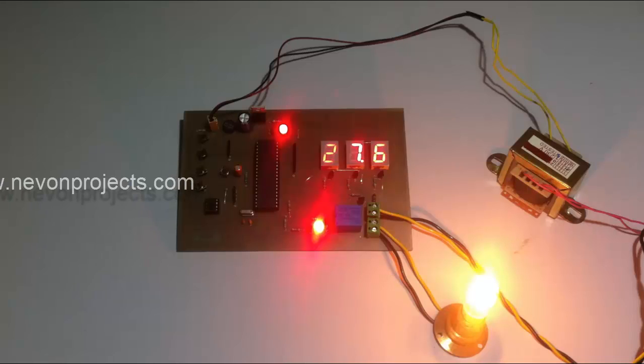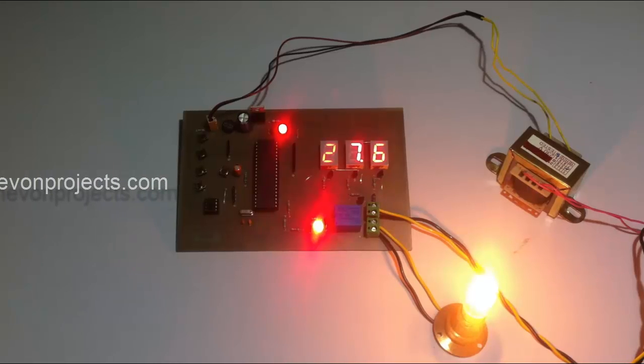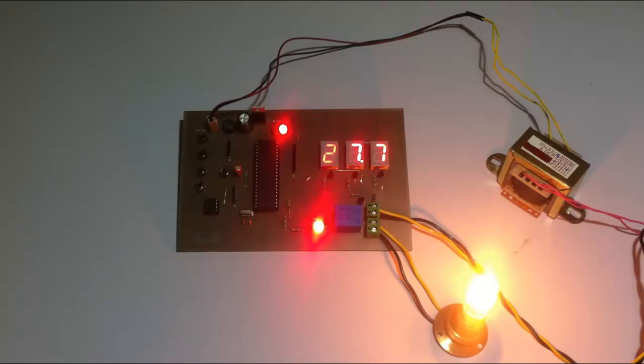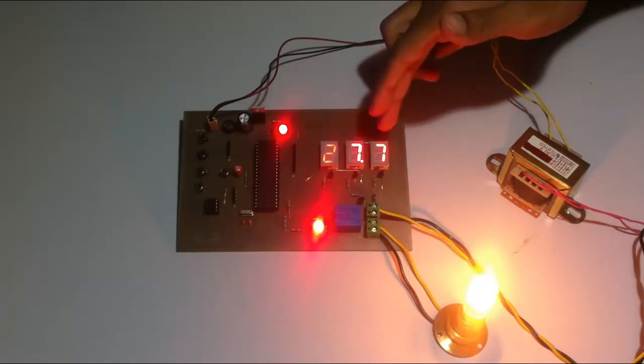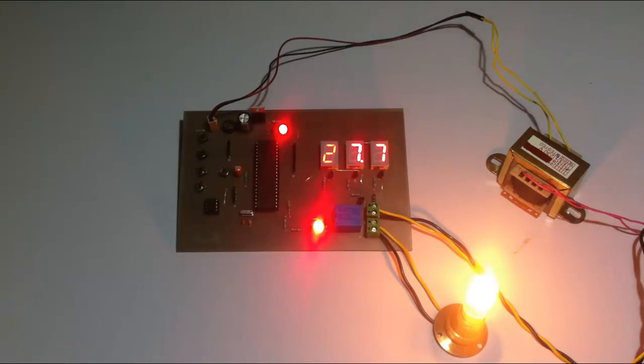Now let's set the temperature we want within the incubation chamber, using the push buttons here. Our system is programmed to provide 0.1 degree accuracy, so it shows temperatures with 0.1 accuracy. Current temperature is 27.7 degrees Celsius, and the increase or decrease in temperature is shown accurately with a 0.1 degree difference.